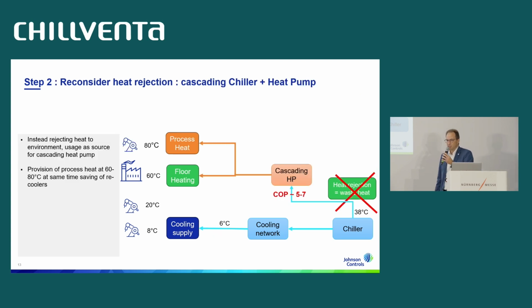Going further is thinking about cascading the system. So if you have a system already installed, you have a typical chiller and you have your heat rejection, and you have a heat demand. Why not do a cascading by putting a cascading heat pump on top? Instead of using heat rejection, use this as a source for the heat pump. And this can deliver process heat and floor heating in a very easy way.